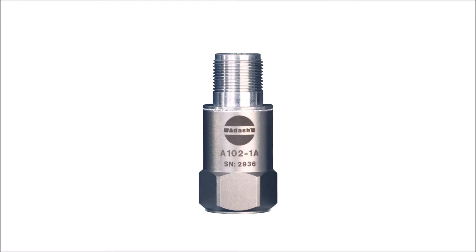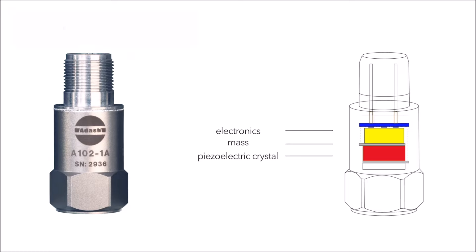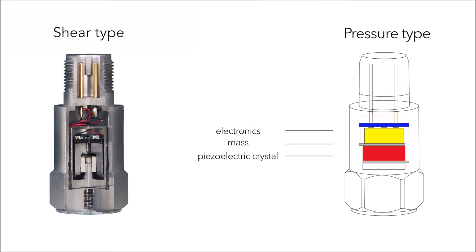The most commonly used acceleration sensor in industry is a piezoelectric acceleration sensor. It is an electronic device which in a very simple way looks like this inside and like this in reality. A piezoelectric crystal generates an electric charge when it is deformed, meaning compressed or stretched. To ensure deformation of the piezoelectric crystal, there is some preloaded mass on it.